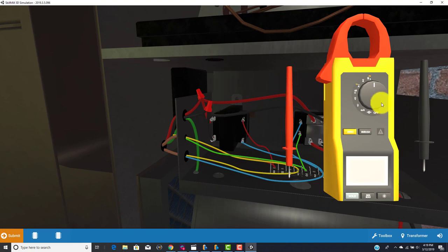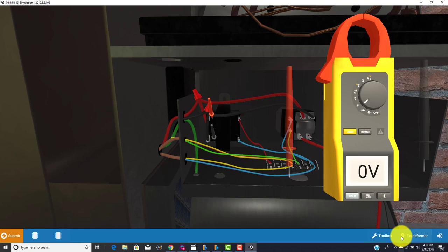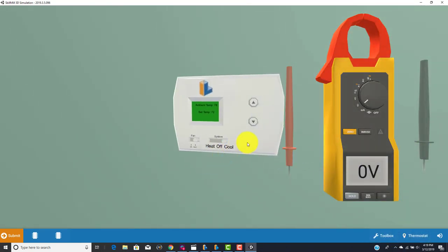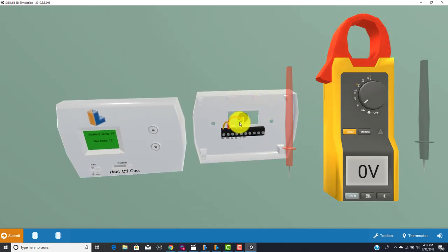Here's a critical thing. We no longer are putting the multimeter where it needs to go. You've got to do that yourself. So here we go. Now I turn the multimeter on to check for volts. I'm checking the primary side of the transformer. I'm not getting a reading.